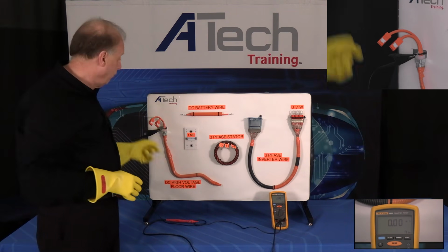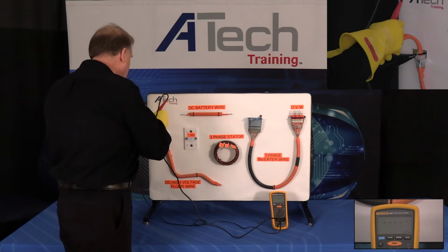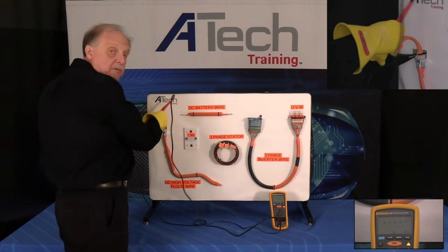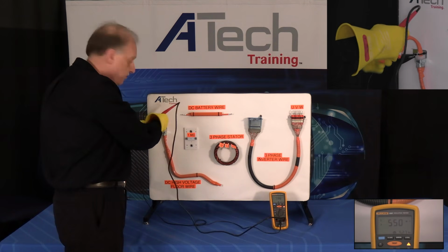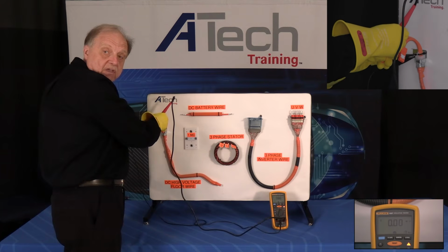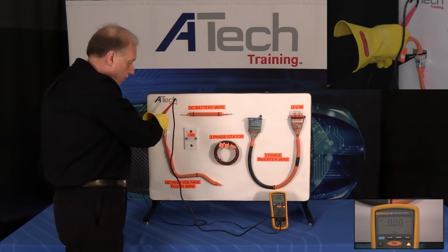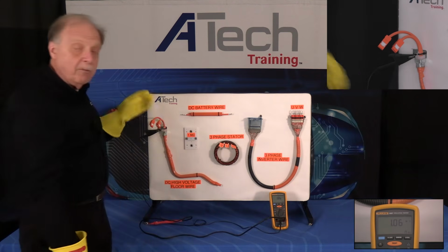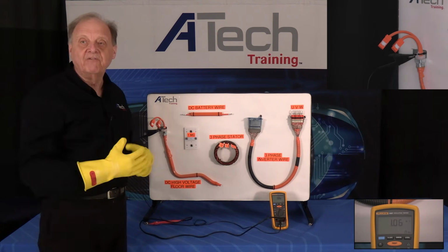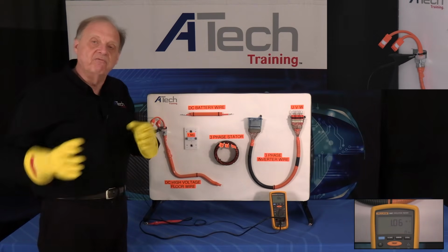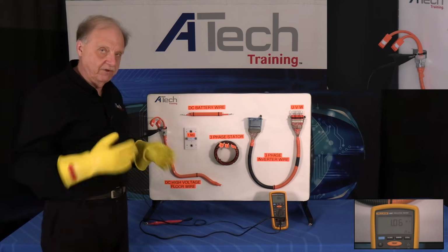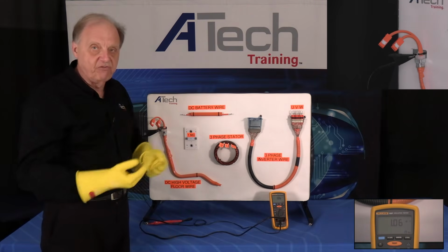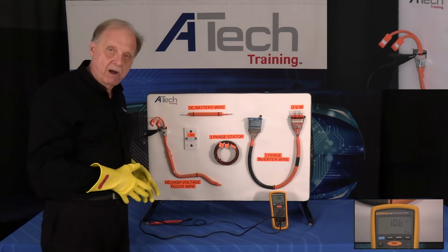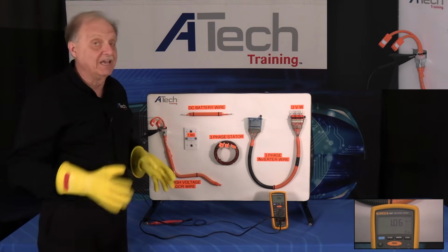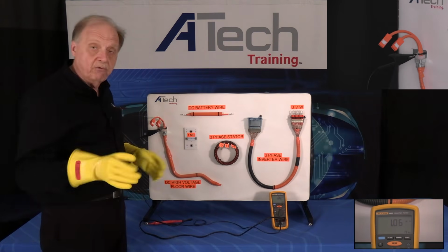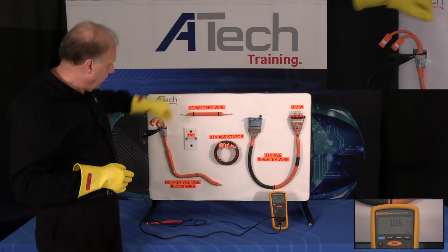So what I want to do is make sure, if I'm doing this again, let's see if I get a good connection here. Sometimes you have to worry about your connection. Notice that it says 550, but if I go over and look at it again and get a good connection, which I didn't, it says zero, which means there is a problem with the wiring here, so we know that we have an issue. It's not continuity, because I'm putting 527 volts onto the circuit. I want to see the resistance there. If there's no resistance, we have a problem. If it goes to zero, we have a problem. It's not like a conventional meter where that's continuity. The other thing to keep in mind: the cable we're looking at here is very similar to this.